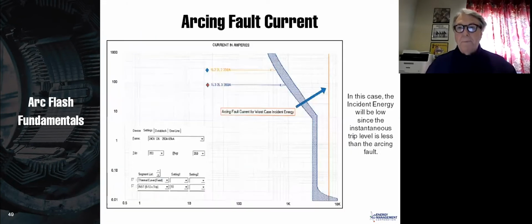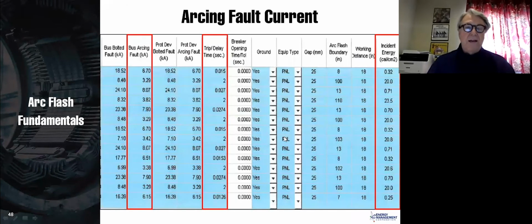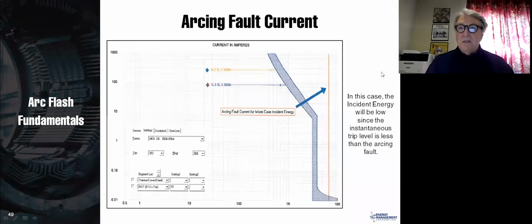Here's an example. Again, this is a real example. Here's our, I think this is a circuit breaker. So there's your time delay over current, there's your instantaneous, and here is your arcing fault. You can see that that arcing fault is high enough that the instantaneous trip on the breaker is going to trip. It turns out that that is this first line here. It's going to trip instantaneously, so our trip delay is 0.015, and we have very low calories. Now let's look at the second line.